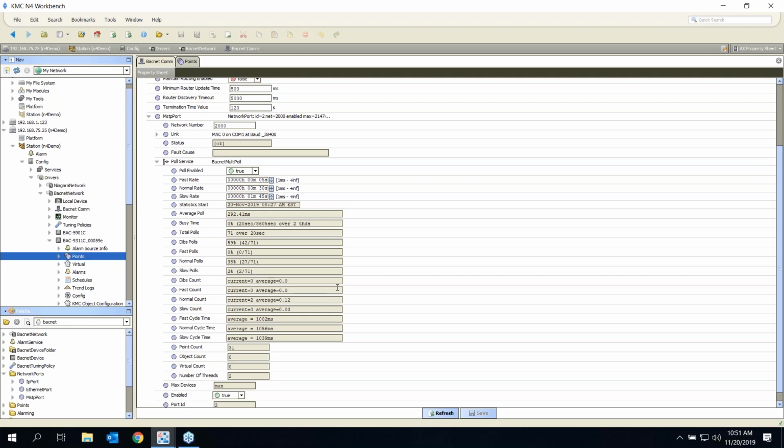And that's going to kind of go towards what your minimum cycle time is, right? So if you put a history extension on 1,000 points in your station, then you're going to have 1,000 points in the driver that are subscribed all the time, regardless of whether anyone's looking at it. And depending on the driver and the speed and so forth, that'll kind of dictate what your initial cycle time is, right? And then if we want to transiently look at things in graphics, that'll add more things into the queue and possibly prolong the time.